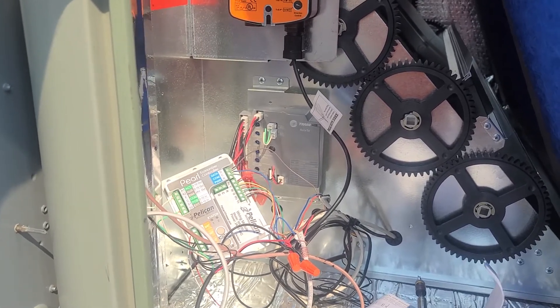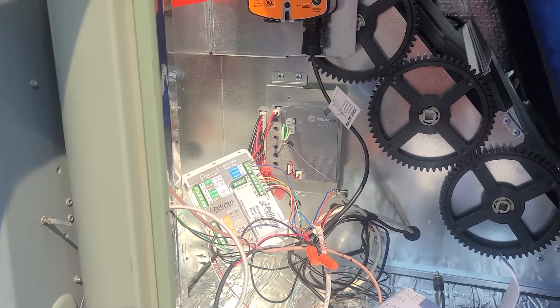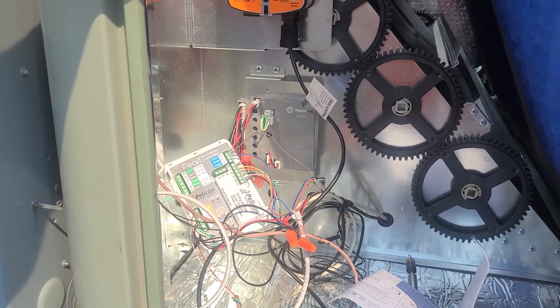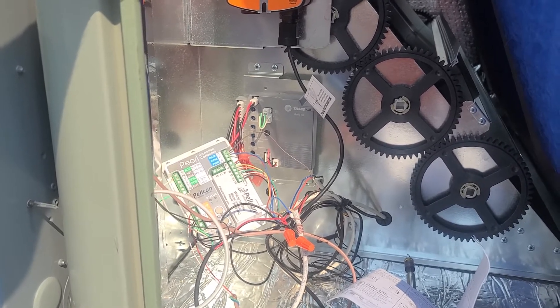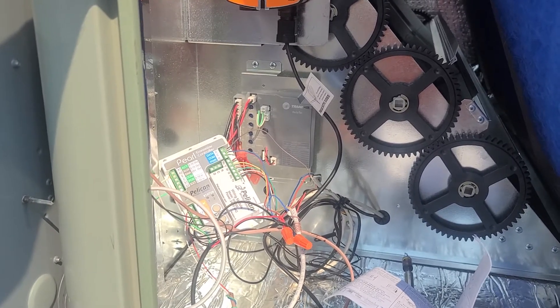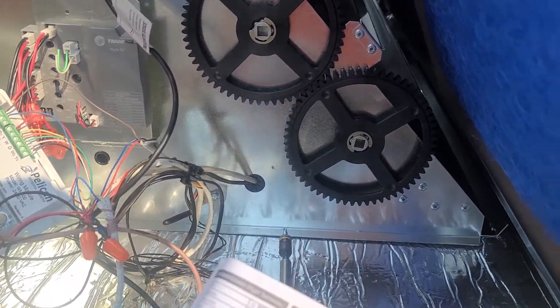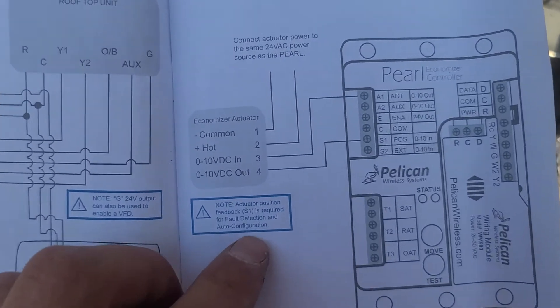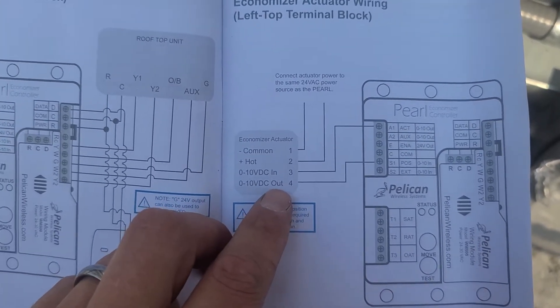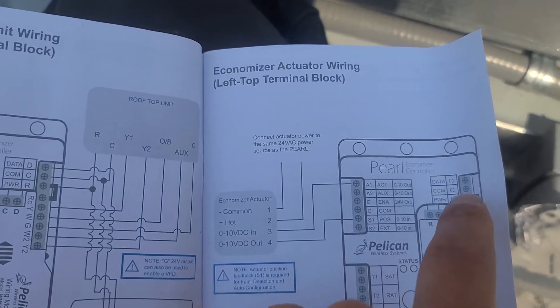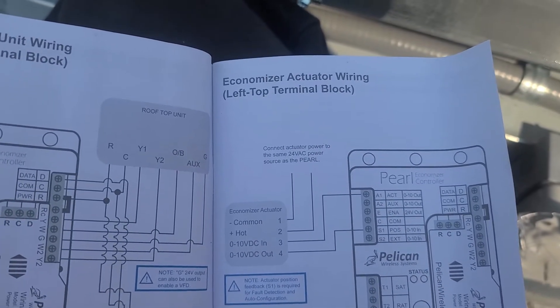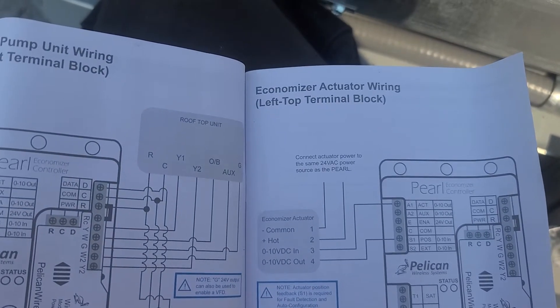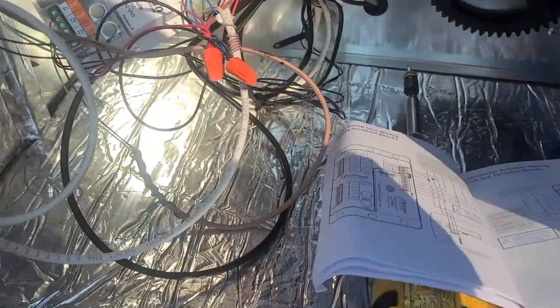You're going to be bypassing every economizer control that came OEM with the unit. This unit can actually be operated for economizer controls and you can also use it for controlling like a VFD. If you're upgrading an older motor to a VFD or anything like that, you can actually tie it into this and control it as well. It gives you really good directions. For the economizer, it tells you pretty basic: you're going to have your 24 volts, and I usually just tie them in over here with the common and the power, and then you have your in and your out for just the control going to the economizer.